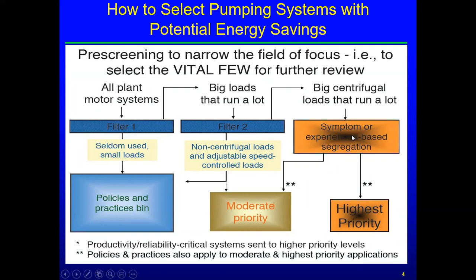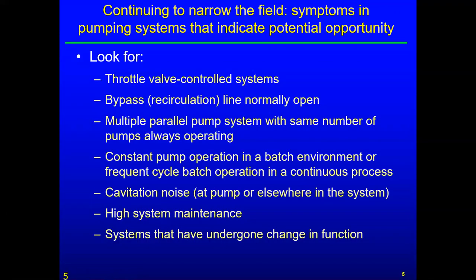The symptoms for pumping systems include throttle-valve-controlled systems. If your control valve is always modulating between 20% and 60%, the pump is a little bit too large. You can control a pump with a VFD instead of a throttling valve, and there's generally good energy savings there.